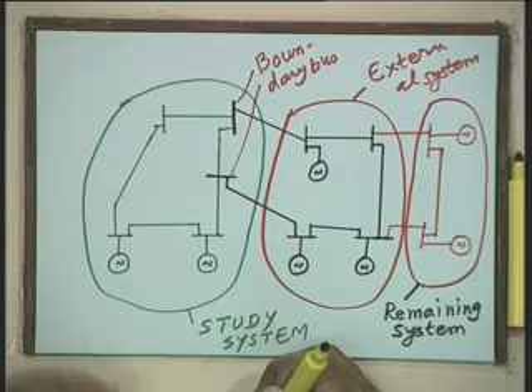In this modal analysis technique, first one has to obtain a linear model for the complete system. With this linear model you obtain the eigenvalues of the system, and then using this information about the eigenvalues you eliminate certain modes and retain only those modes which have a significant influence on the system dynamic behavior. There may be some modes which decay fast, you can just ignore them. Those modes which have a very low time constant can be ignored, and those modes which have a high time constant, you retain. Because we are studying stability, this is a slow phenomenon. We always study in 2 seconds, 3 seconds, and modes which decay very fast, in a fraction of a second, you can ignore.